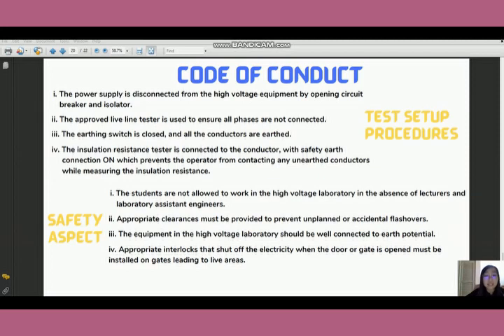As for the safety aspects, first, students are not allowed to work in the high voltage lab in the absence of the lecturers or the laboratory assistant engineers. Second, appropriate clearance must be provided to prevent unplanned or accidental flashover. And third, the equipment in the high voltage lab should be well connected to earth potential.